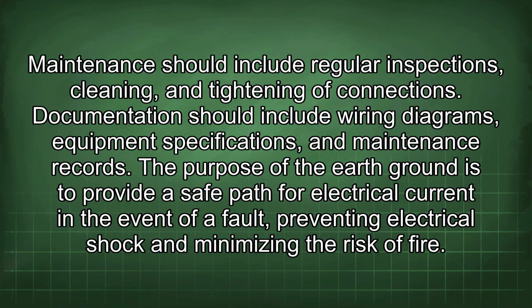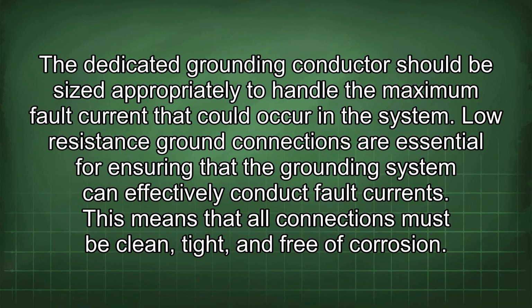The purpose of the earth ground is to provide a safe path for electrical current in the event of a fault, preventing electrical shock and minimizing the risk of fire. The dedicated grounding conductor should be sized appropriately to handle the maximum fault current that could occur in the system. Low resistance ground connections are essential for ensuring that the grounding system can effectively conduct fault currents. This means that all connections must be clean, tight, and free of corrosion.